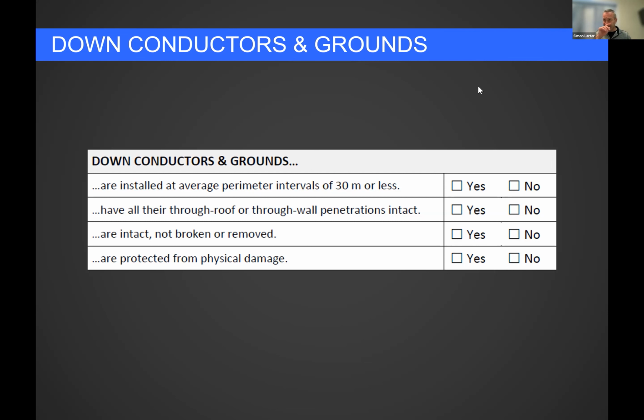That 2 meter distance is usually considered the maximum flashover distance for lightning current to jump to a different grounded system. It's very rare for flashover to go farther than 2 meters. So functionally, we'll generally bond all grounded bodies within 2 meters of our conductor to our system, creating equipotential so jump flashover doesn't happen. That's probably where that number came from in the CE code.